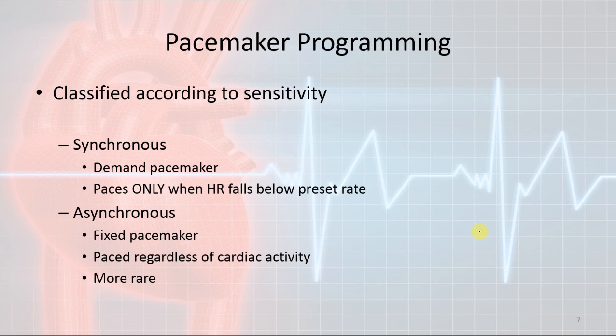When programming a pacemaker, we need to classify a couple different types of pacemakers. One type of pacing that a pacemaker will perform is synchronous pacing. If a pacemaker is synchronous, that means it works with the heart. That basically means that a synchronous pacemaker will take its cues from the heart. It is a demand pacemaker, and it will pace only when the heart rate falls below a preset rate or when it's programmed to do so. An asynchronous pacemaker is something that's called a fixed pacemaker, and what that basically means is that it is going to pace regardless of cardiac activity.